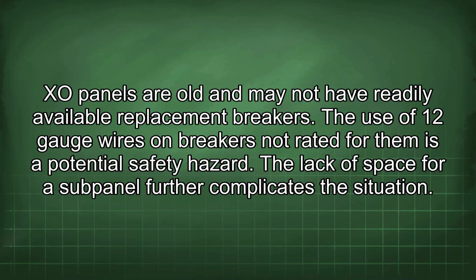XO panels are old and may not have readily available replacement breakers. The use of 12-gauge wires on breakers not rated for them is a potential safety hazard. The lack of space for a subpanel further complicates the situation.